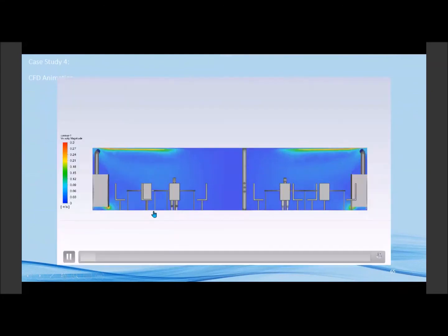I would determine this is not as effective. You can see there's still a lot of mixing going on here. They're planning on rotating some of these pipes and having some distribution duct on there, but it gives you kind of an idea. Not everything was great. This air just rolled right across the ceiling, as you can see. And the goal really would have been to have this air come across the ceiling and gently fall like rain.